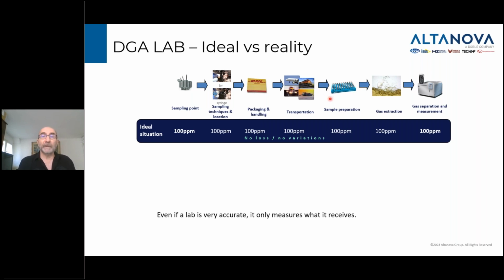When it gets to the lab, the sample will wait, depending on the lead time of the lab. Then they have to prepare the sample, extract it, and mostly use GC to separate the gas and measure it. So when you look at that process, in an ideal situation, if you had 100 ppm of gas in that transformer, you would like to see the results coming out of that GC at 100 ppm. That's the ideal situation, and it never happens. There's too much handling and too much time waiting to have absolutely no error in managing the sample and no chance of losing gases.